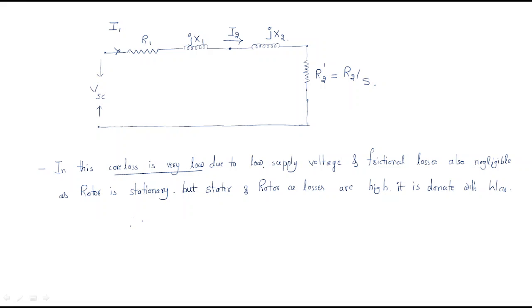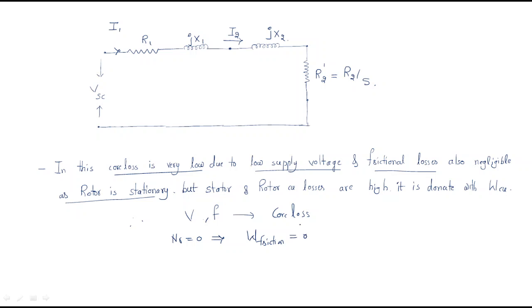Core loss is very low because voltage and frequency both affect core loss. Frictional loss is also negligible since the rotor is stationary — rotor speed is zero, so there is no friction. However, stator and rotor copper losses are high, which is why we perform this test.